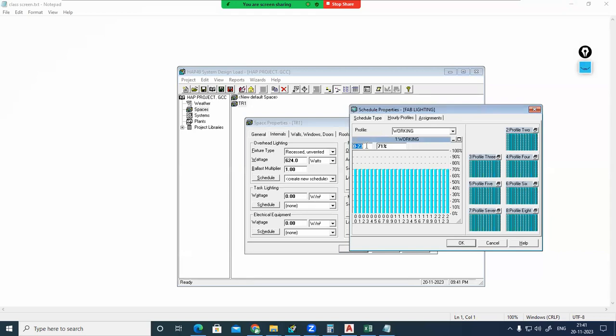But the easiest method, I will show that. Easy method. See, declare that my office will be working from 9. So I'm providing 0 there, 0 to 7 a.m. Now no one will be using light fitting. So the lighting load I am providing 0. But 8 a.m., even if the office is at 9, people might start reaching office before that. So 8 a.m., the people might be consuming 50. But if you want for safety, you can consider, for example, morning 12 a.m. to 7 a.m., 10%, 20% lighting load. If you want to consider, you can provide that, but I'm not considering it. Working time lighting load only I'm considering for AC. 8 a.m., 50% of people will be working.